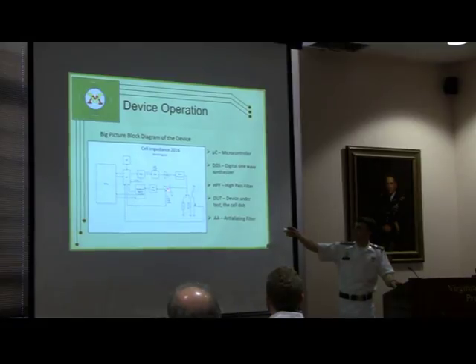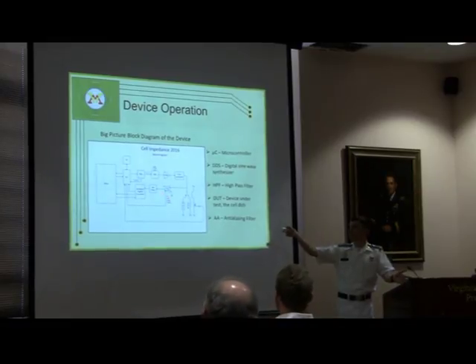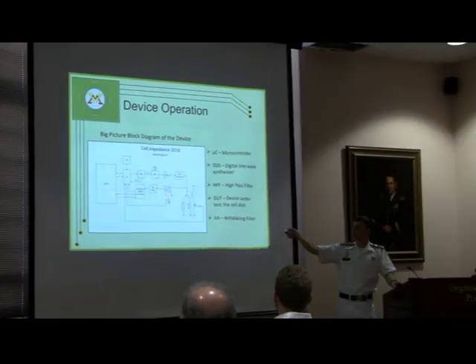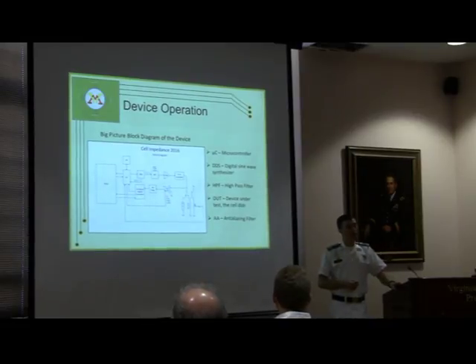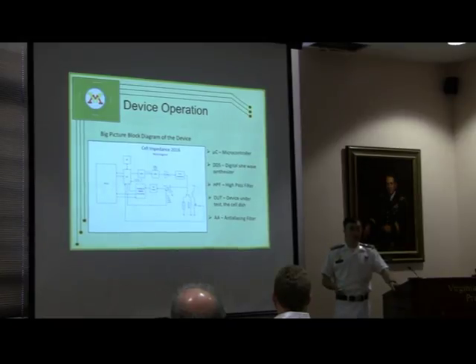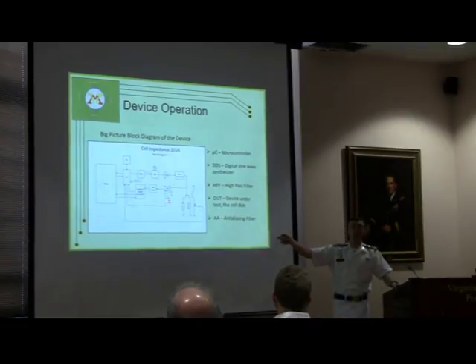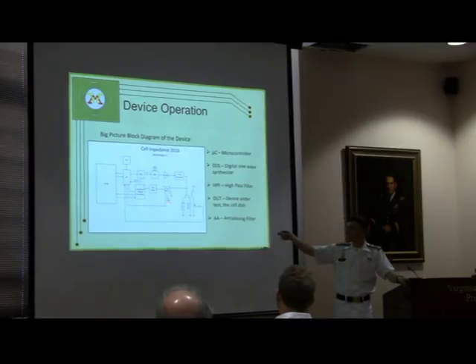So what happens essentially is there are 4 different levels of amplification. You can keep it at ×1, so we leave the waveform the way it is, we don't do anything to it. Multiply by 10, multiply by 100, or multiply by 1,000. So the way it knows which one to multiply it by with is the computer is actually going to get the data from the lowest amplification first. It's going to see if that data is usable, if it can actually distinguish a waveform from it. If it can't, it bumps up the amplification, runs it again. So we do that routine until we find an amplification that works for the particular waveform we're testing, or we've hit the limit of the amplifier's power. So if we reach 1,000, there's nothing higher we can go from that. So that's going to be the last one that it sticks with.